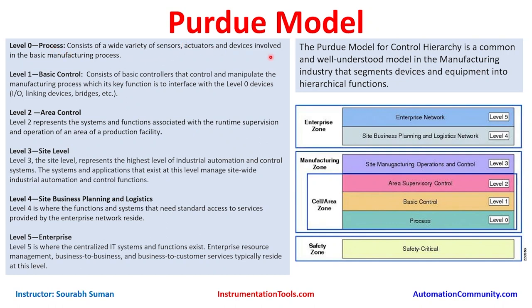Level 0 consists of a wide variety of sensors, actuators, and devices involved in the basic manufacturing process. Sometimes safety-critical instrumentation, or SIS, is also kept in this model, though Cisco has kept it in a completely separate zone. Level 0 is the basic level where all field instrumentation resides, with communications happening over 4–20 mA or proprietary protocols such as Modbus, DNP, IEC, or fieldbus.